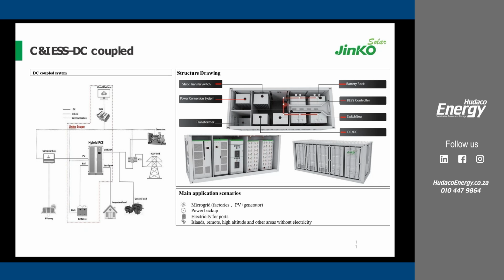The purpose of the isolation transformer is to get our neutral, since this is how we transition from delta to Y configuration, and it also assists in protection against reverse currents. Then we have the static transfer switch, either STS or thyristor, which is responsible for the seamless switching I mentioned, that is the MS level switching.